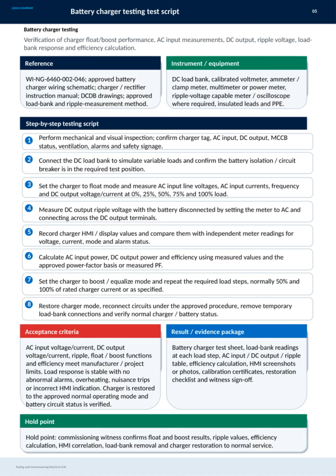Next, we set the charger to float mode and measure AC input voltages, currents, frequency, as well as DC output voltage and current across various load levels from 0 to full load. It's important to also measure the DC output ripple voltage with the battery disconnected, using AC settings on the meter. We then record the charger's own display readings and compare these with independent meter measurements for accuracy.